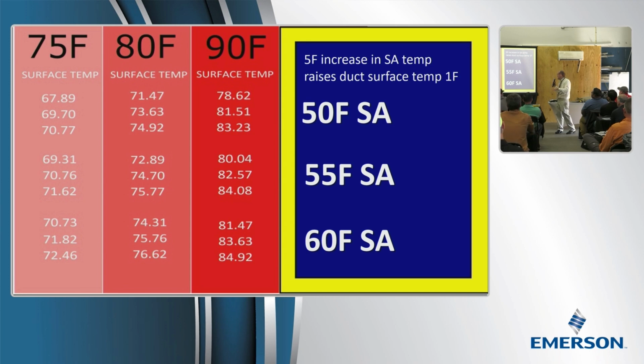outside for whatever reason, then my point is that if I'm a service technician and I'm expected to do something about this sweating air handler and these sweating ducts, well, you can take the static pressure and check and see, is it restricted? Is there a dirty filter? You can look at all of it. It's moving air. It's just sweating like a pig.